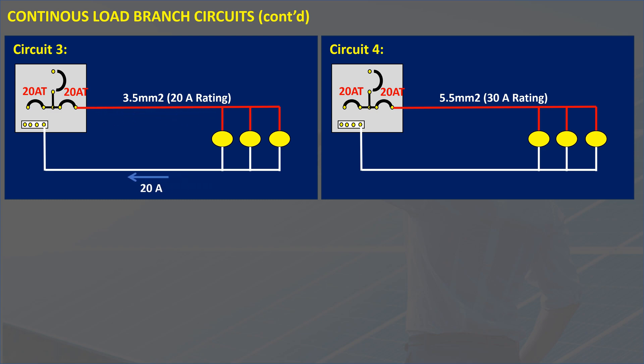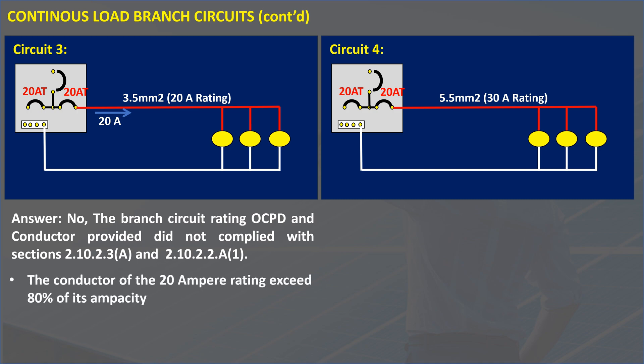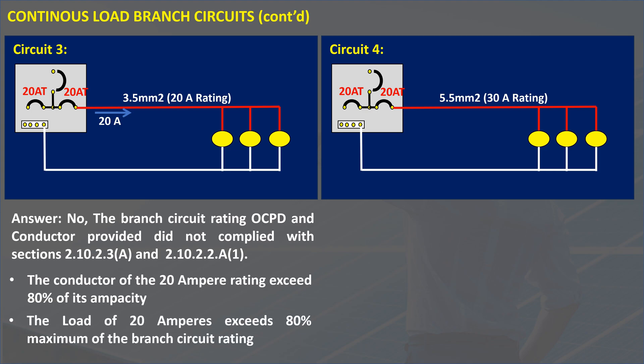How about circuit number 3? A 20 amperes continuous load is connected to a branch circuit rated at 20 amperes with a conductor rated at 20 amperes. Is this circuit compliant with the code? No. The overcurrent protective device of 20 amperes and the conductor provided did not comply with Sections 2.10.2.3 A and 2.10.2.2 A1. The conductor of the 20 amperes rating exceeds 80% of its ampacity, and the load of 20 amperes exceeds 80% maximum of the branch circuit rating.